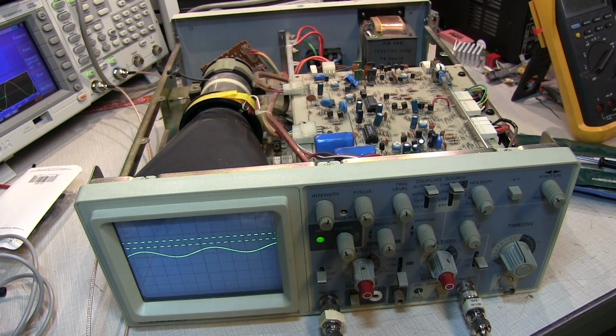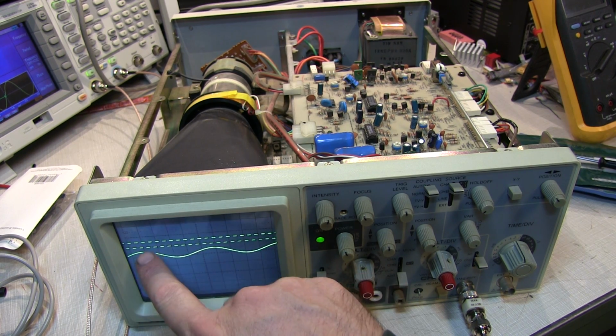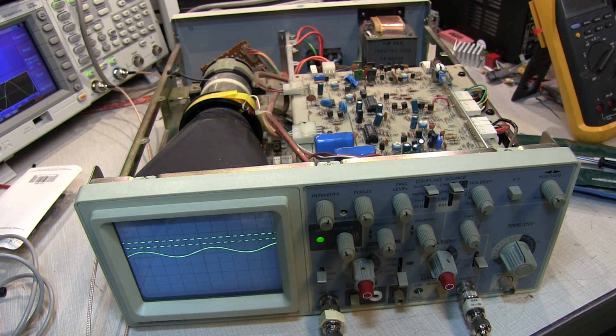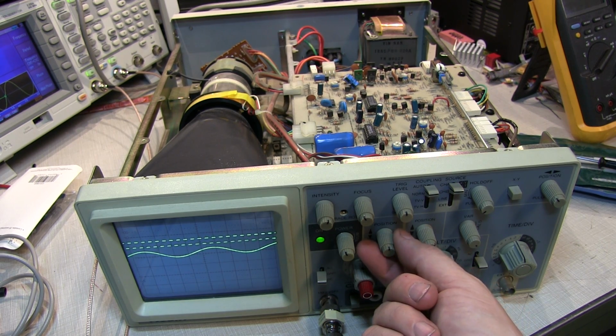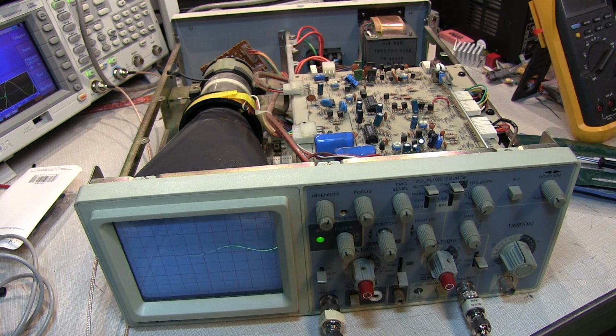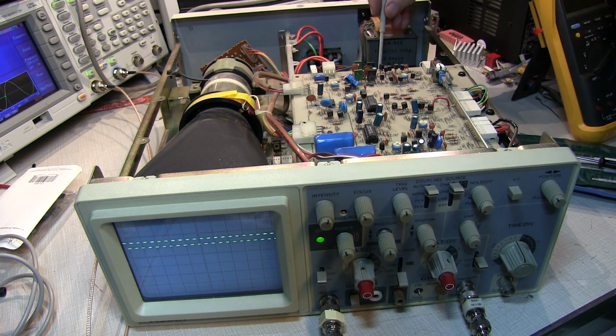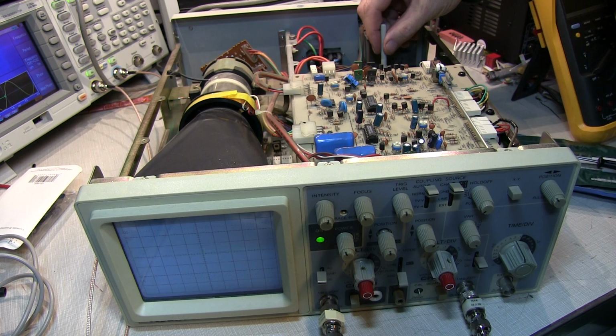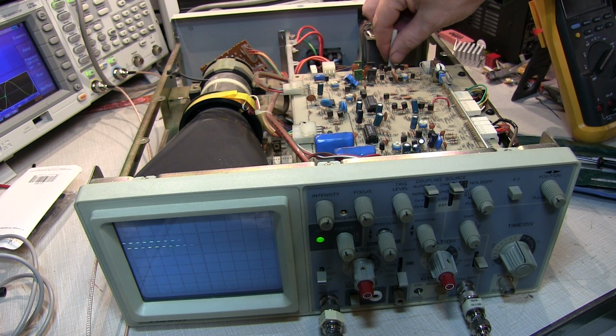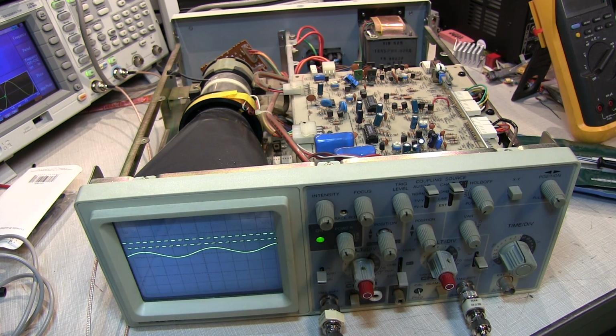Okay, the last adjustment for the trigger on this particular scope is the alternate trigger. So I've got a 1 kilohertz sine wave and a 10 kilohertz square wave, per the manual, applied to channel 1 and channel 2. And we put the scope into alt trigger mode. You can see those signals are actually not being triggered right, so this circuit actually does need adjustment. So we'll go in here and make that adjustment. And now we can see both those waveforms are triggering properly. So we're finished with the trigger section.